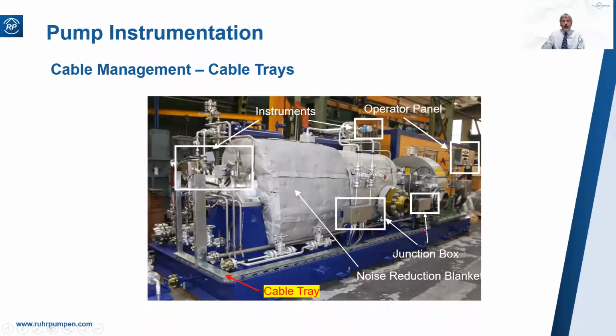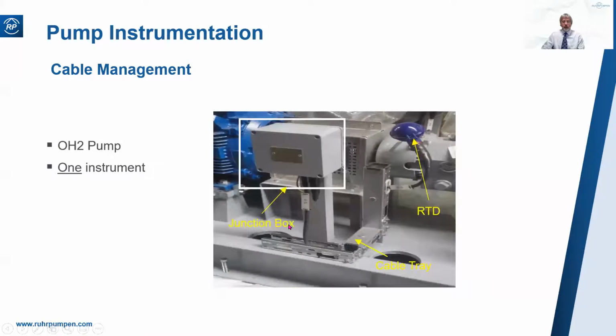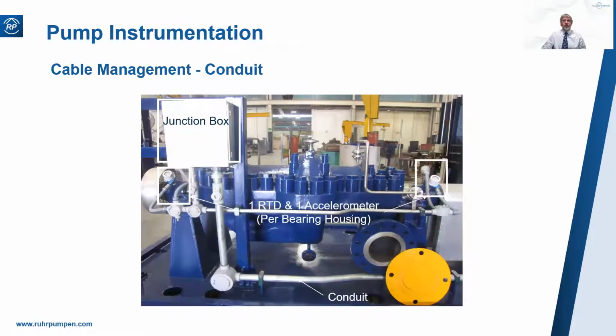Here we see quite a big pump and cable trays. All the instrument runs running in cable trays. Quite neat. Now here we see a simple OH2 pump with only one instrument, an RTD. But still, there's a requirement in the spec to cable it to a J-box at skid edge. I would question whether that is really necessary, or is it blind adherence to the specification. To my mind, it's as easy to connect to this RTD here as it would be to connect it here in the J-box. Here's a sizable pump with all the wiring run in conduit. Obviously a North American installation.